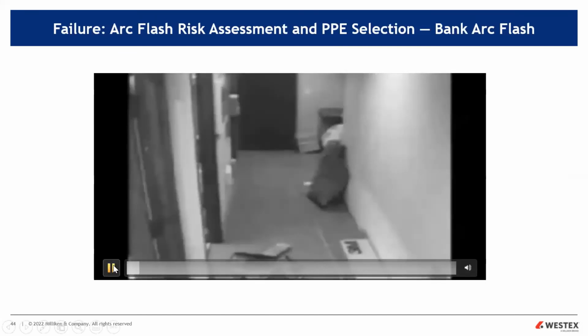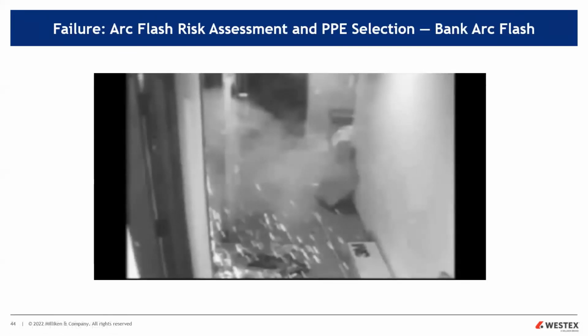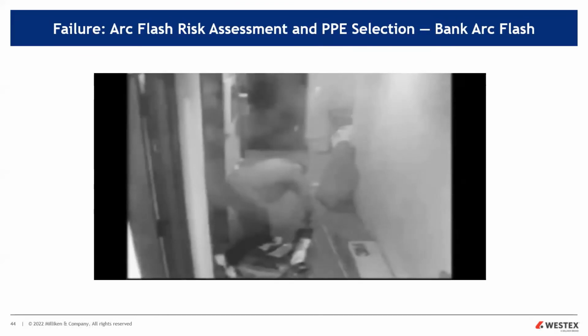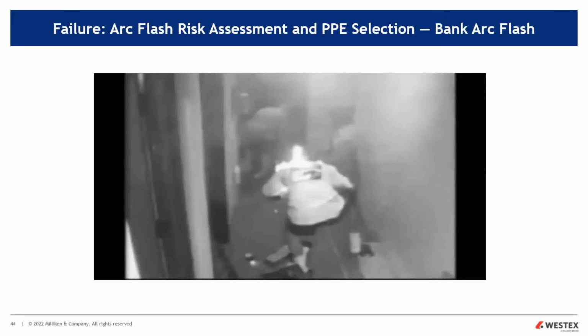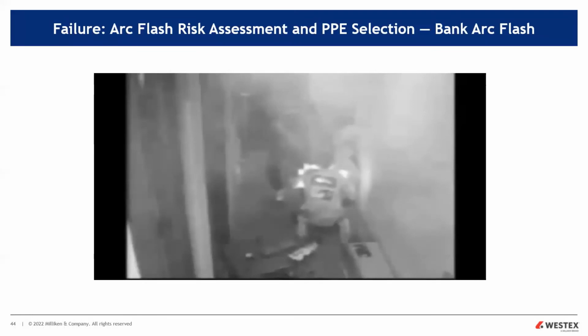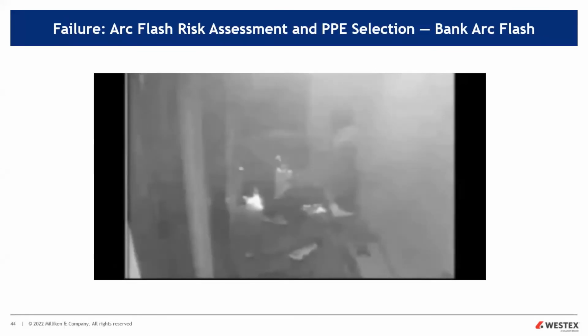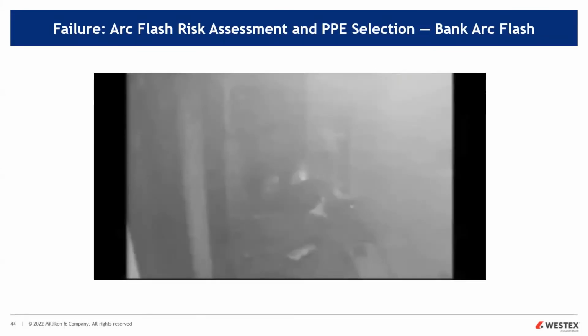This is at a bank. What could be in a bank? Well, there's HVAC. We've got an arc flash. This guy comes out first. He's not burned yet. This guy's burned. He's on fire. The first guy that comes out burns his hands patting out his colleague. Now, was the PPE out in the truck and they just had a quick job? Well, this guy was wearing shorts, so I doubt they had any PPE. But it's a scenario where the arc flash assessment was off and the PPE selection was certainly off.